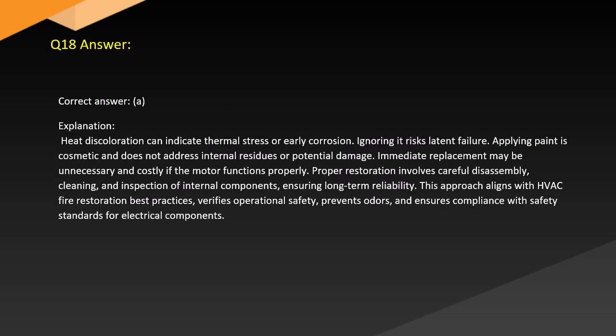Answer. Correct answer. A. Explanation. Heat discoloration can indicate thermal stress or early corrosion. Ignoring it risks latent failure. Applying paint is cosmetic and does not address internal residues or potential damage. Immediate replacement may be unnecessary and costly if the motor functions properly. Proper restoration involves careful disassembly, cleaning, and inspection of internal components, ensuring long-term reliability. This approach aligns with HVAC fire restoration best practices, verifies operational safety, prevents odors, and ensures compliance with safety standards for electrical components.